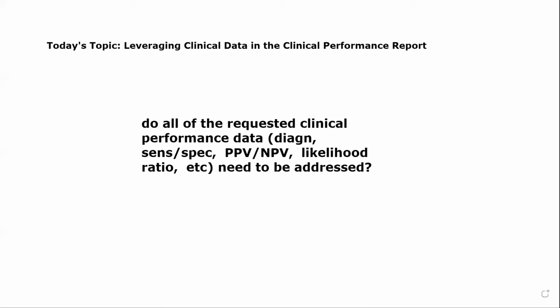You want to make sure that that's all done objectively and very transparently, so it doesn't appear as if you've left out clinical performance data that doesn't support your device as being considered state of the art. You would want to make sure that you're being very objective and very clear about your choice and justify that within the PER.